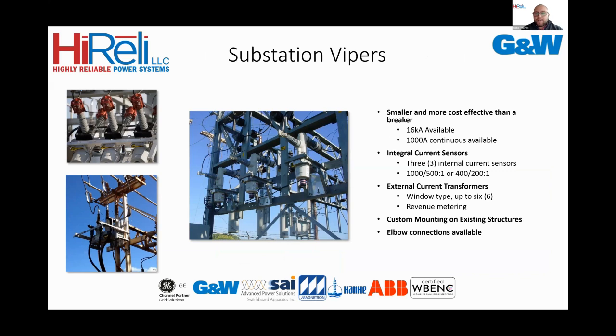So with the higher ratings that have become available at G&W, going up to 16 kA interrupting and 1,000 amps continuous current, we're also able to use Vipers in substation applications in place of a breaker, where it might be more cost effective and have a smaller footprint. We do have the integral current sensors. So there's 3 current sensors molded within the Viper module. You can do 1,000 or 500 to 1, or 400/200 to 1. Depending on which two of those you pick, that 1,000 to 500 is field changeable. Same thing with the 400 to 200 to 1.